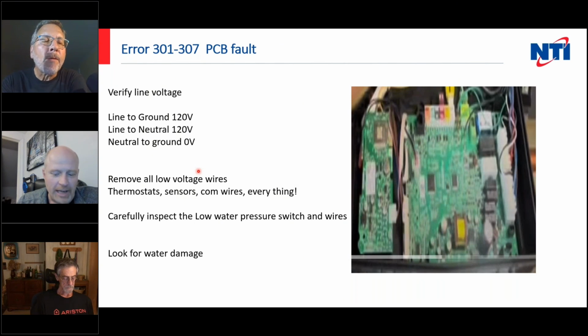We have had boilers in the past where people have wired, by accident, domestic hot water to thermostat. Instantly, you get an internal fault on the boiler control, and as soon as you remove the wires, the problem goes away. Sometimes it's easy to do. Sometimes the terminal strips are hard to read. The boiler rooms are not well lit.